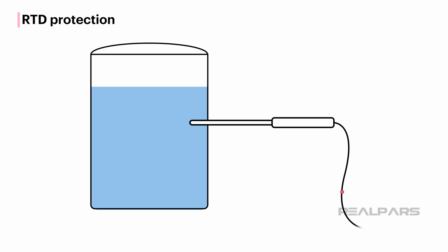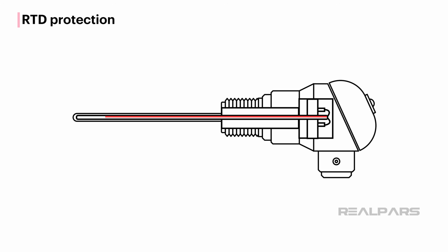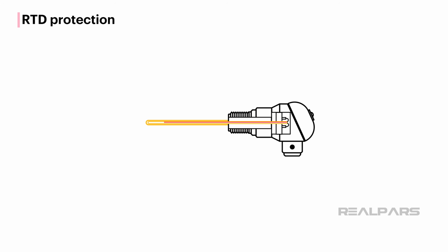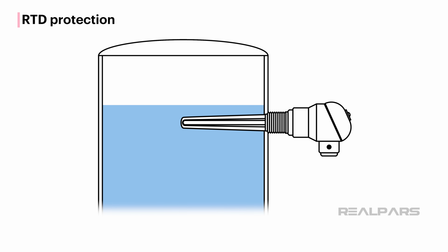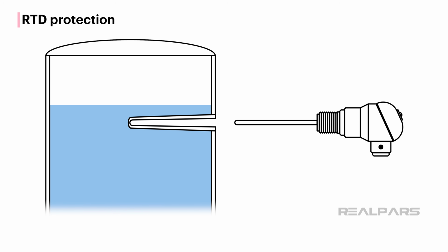As you can imagine, it's not practical to expose an RTD directly to whatever temperature process we're attempting to measure, and more than likely, the ambient conditions are not friendly. An RTD needs protection. A connection head is used to connect the RTD leads to the transmitter. The connection head also protects from nasty ambient conditions. Further protection is provided by inserting the RTD sheath into a thermowell that is permanently housed in a pipe or a vessel. The thermowell protects from potentially damaging process fluids. The RTD can be easily removed from the thermowell without interrupting the process.